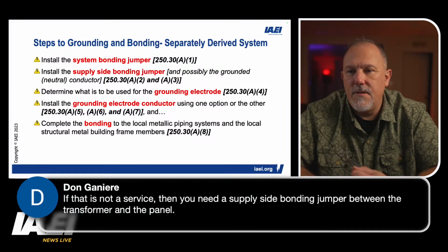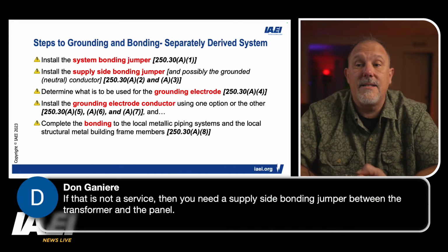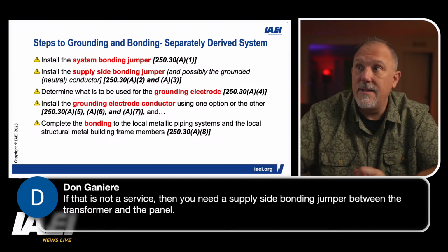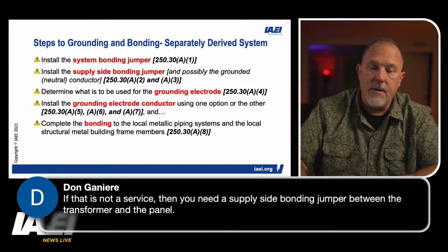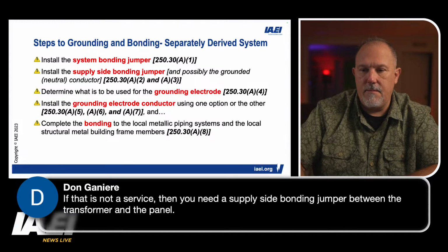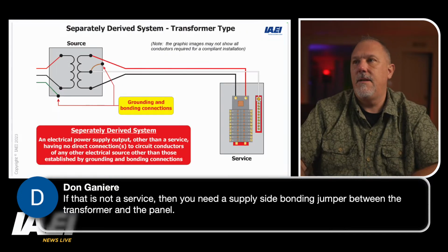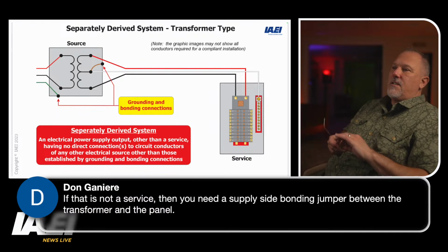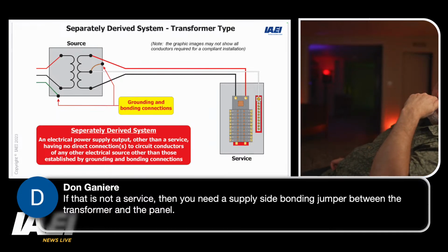If that is not a service, then you need a supply-side bonding jumper between the transformer and the panel. That is exactly right. You are exactly right. Let's go back to that image. But you know what I don't like about this image is it has it as a service.